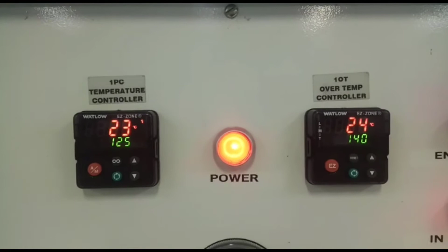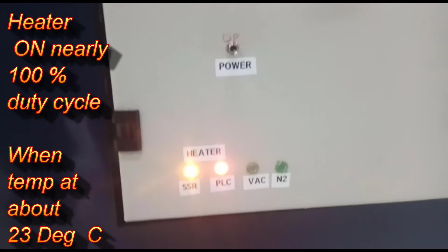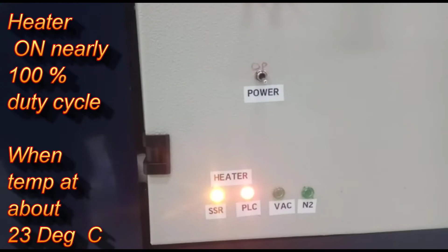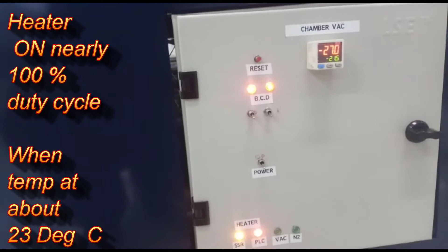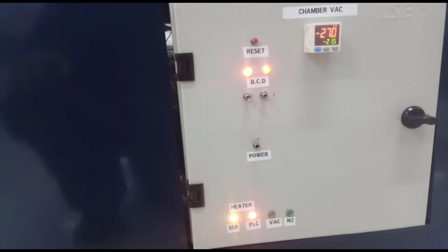Right here, an oven, a vacuum oven to be specific, and it needs to be tied to a PLC. There were a couple of things that were easily doable. One was the PLC could easily take control through an isolation device, either a relay, to take control of the SSR, the heating SSR's controls. So that was a no-brainer.